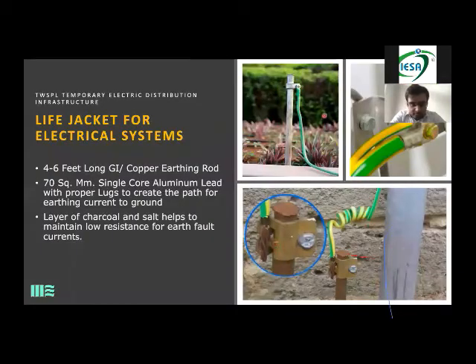In the same way, the lugs have to be there on the earthing wire, properly tightened with pliers or maybe a spanner, and the connection between the earth rod and the wire needs to be proper, so that if there is any unwanted current, it will take it from this wire into the ground. That is the whole purpose of the earthing wire. So the earthing wire is important, and your way of doing the earthing is also important.